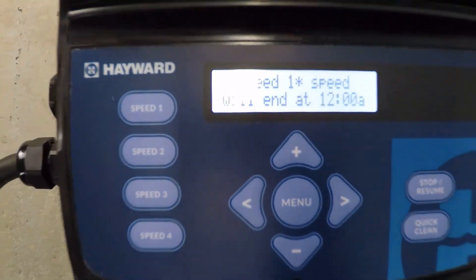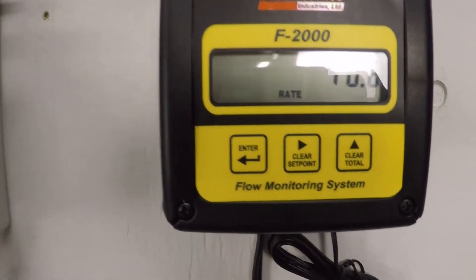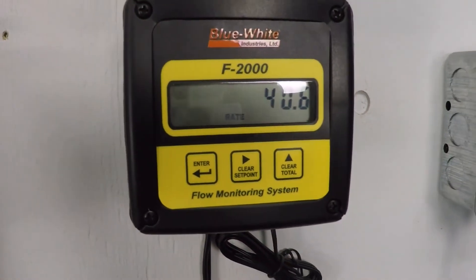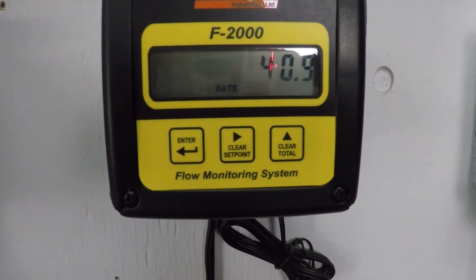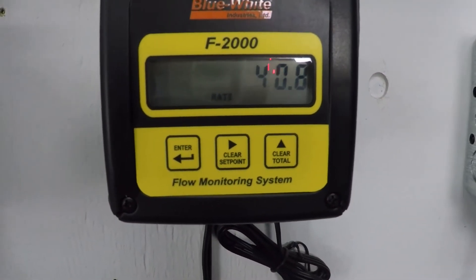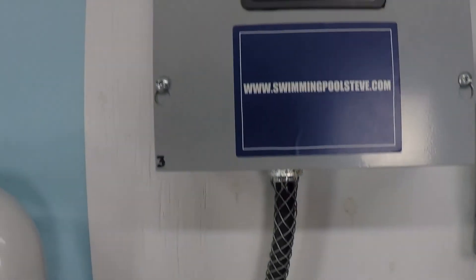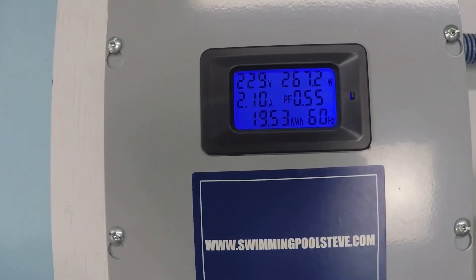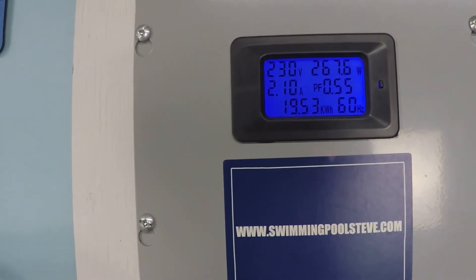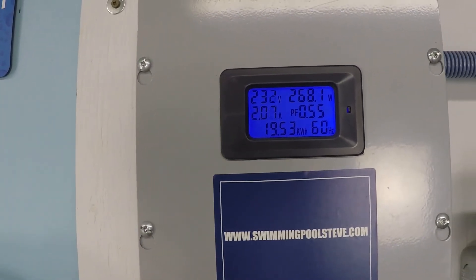As you can see, we are at exactly 2000 RPM. Our flow rate is 40.6 to 40.7 gallons per minute. Power consumption is 267 watts — that's shown in the top right corner. On the left hand side, you can see 2.1 amps of current draw at 230 volts.